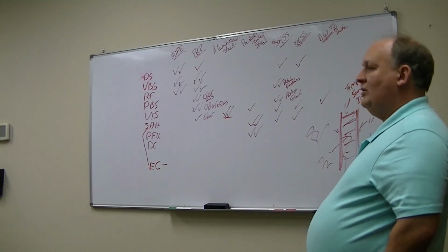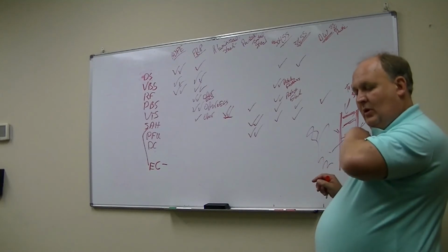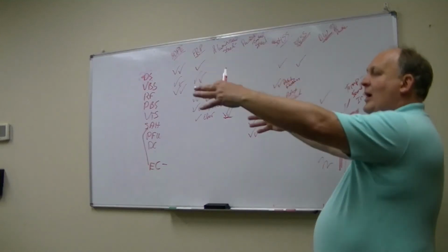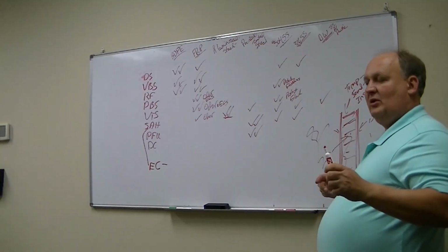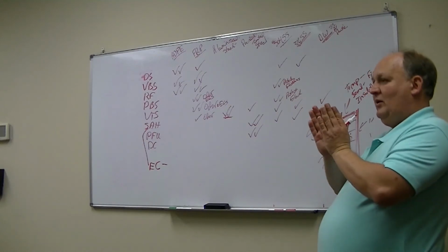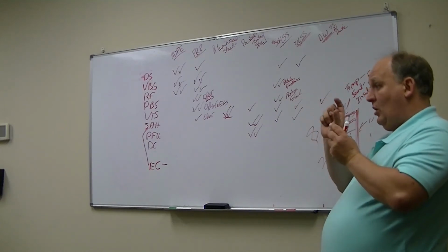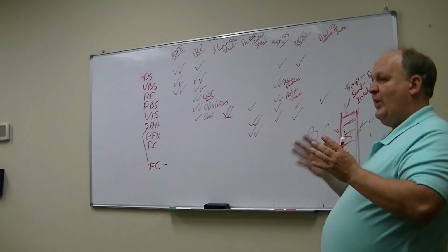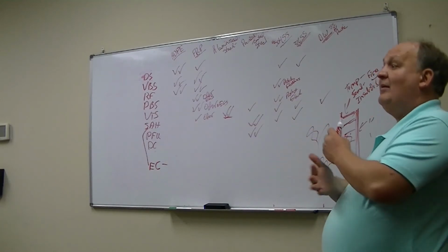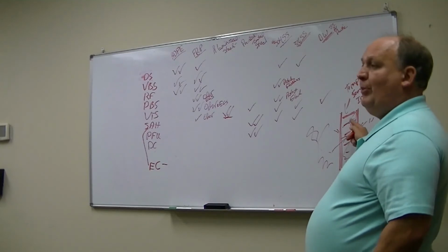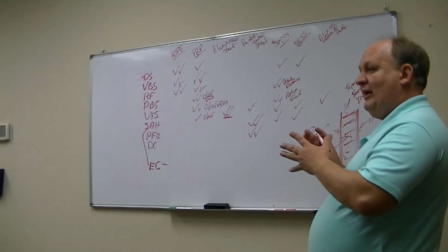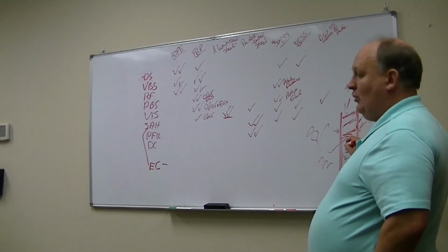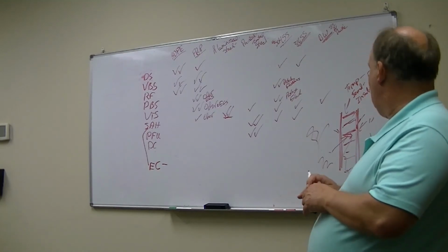But we do have competitors that make a system which is called a post and panel construction. A post and panel construction basically takes aluminum framing, and you make the frame, and we've done a little bit of this ourselves, and then you make these sandwich panels that are made of what's called honeycomb material. It's kind of a board that has honeycomb material sandwiched between them, and they cut those panels out, and they make an air handling unit out of that material. And so the only purpose in that reason for making a double wall is just to make it strong, because they make this material really, really thin and cheap, but the sandwich itself is stronger. Don't worry about that too much.